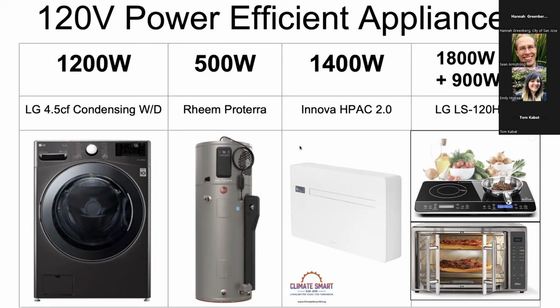And Randy, you said if you want to replace a ducted gas furnace with a ducted heat pump, can you do that on a 100 amp panel? Absolutely. It'll take you between 20 and 30 amps of your 100, and that's more than enough.